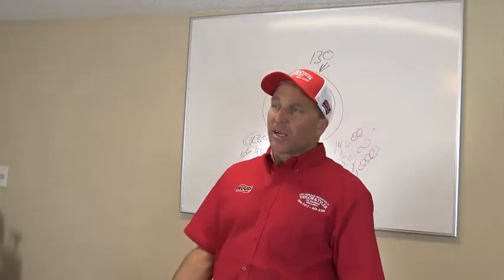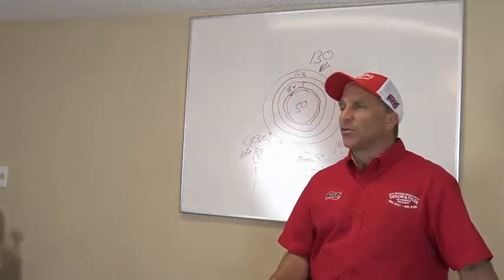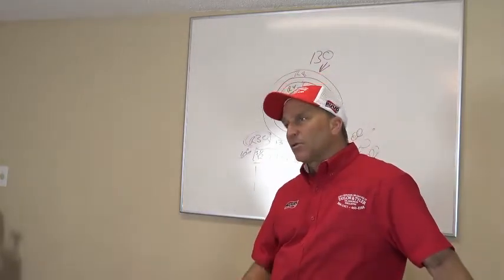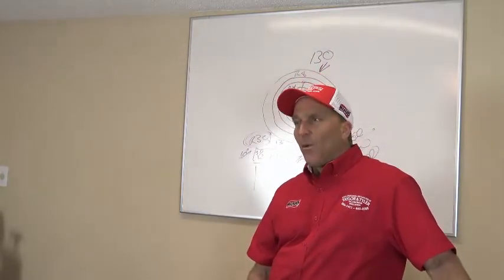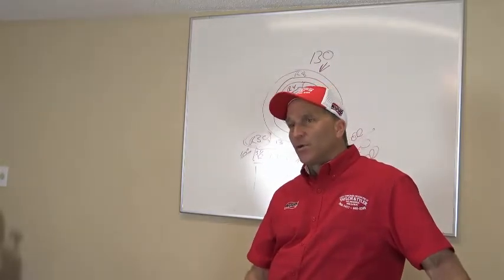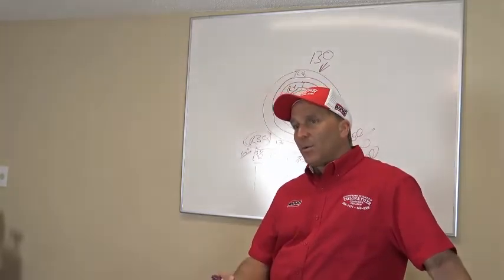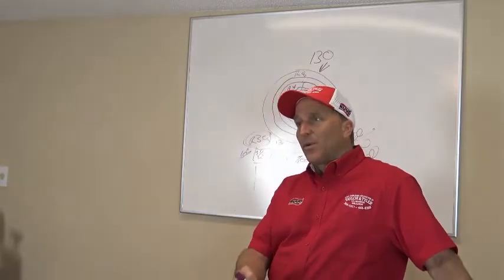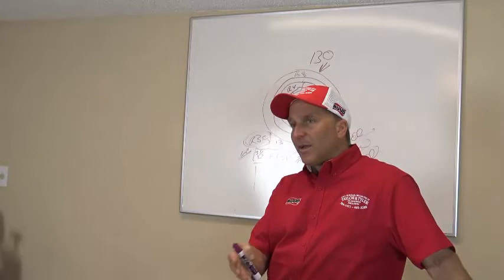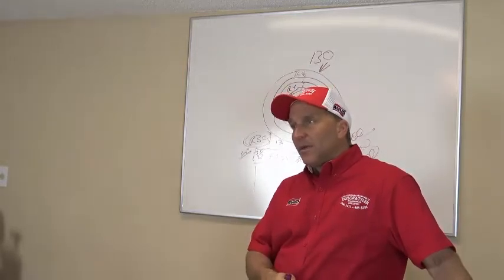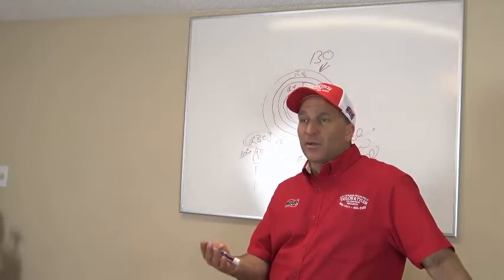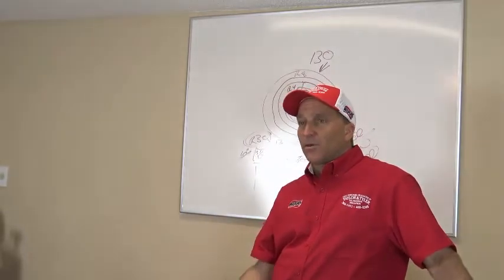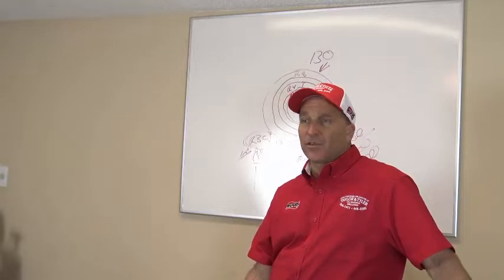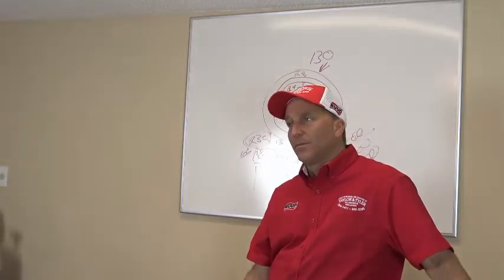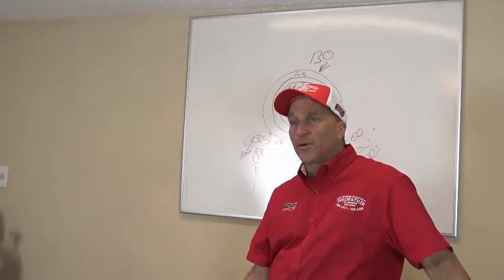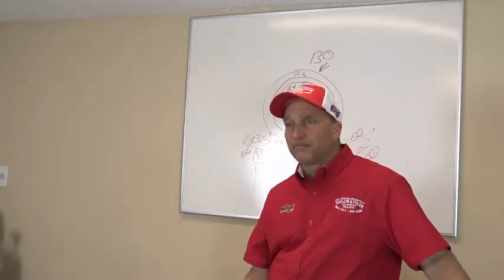Can I make a strong suggestion to you? Let's put a float switch on your drain line, so if ever your drain backs up, it kicks up a float switch and shuts your system off. And that way I can protect your wood floors. I see you just put new carpet in or new wood floors in, and I would really like to make sure that we protect these things by putting a safety switch in there that will kick up and shut your system off. And that makes a lot of sense because I tell you what, it's only $140 for the float switch, whereas new floors are going to cost you thousands of dollars. This is an insurance policy, basically, is what you're doing by putting a float switch in. I got one in the truck. Would you like me to go ahead and do it? Okay.